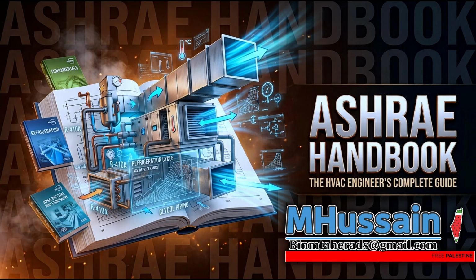It is a violently destructive force. In massive facilities like power plants, university campuses, and large hospitals, they distribute heat using high-pressure steam, which is incredibly efficient for moving thermal energy over long distances. But as that steam travels through the piping network and radiates heat into the building, it naturally cools, so you have a pipe carrying high-velocity gas, but a layer of liquid water starting to pool at the bottom.